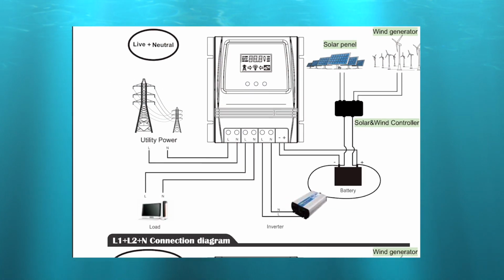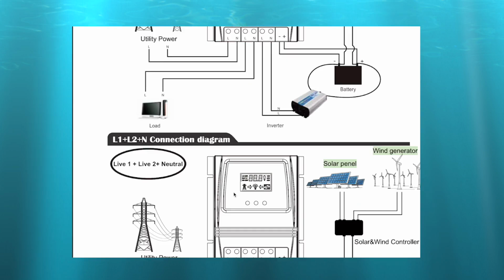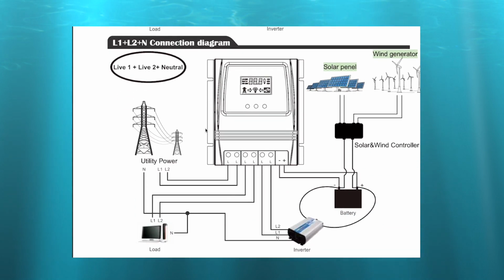This is showing it wired for 120, where you're using line and neutral or hot and neutral through the switch. They don't even show grounds, but I'm assuming you run all your grounds together in a breaker panel. But to hook it up for 240 volts, then it shows line 1 and line 2 going through this switch and all of your neutrals being tied together.